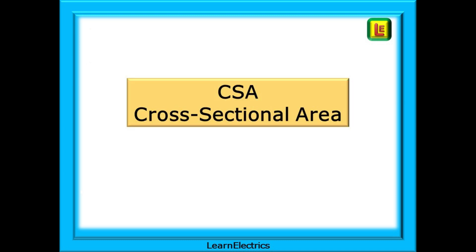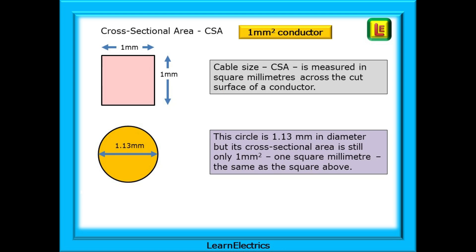The first thing we need to know about our cable is the cross-sectional area or CSA so let's make sure of what this is. Cable size or CSA is measured in square millimeters across the cut surface of a conductor. So what size is a one square millimeter conductor? If this was a square conductor it would be one millimeter on each side. But conductors are round and this circle is 1.13 millimeters in diameter but its cross-sectional area is still only one square millimeter.